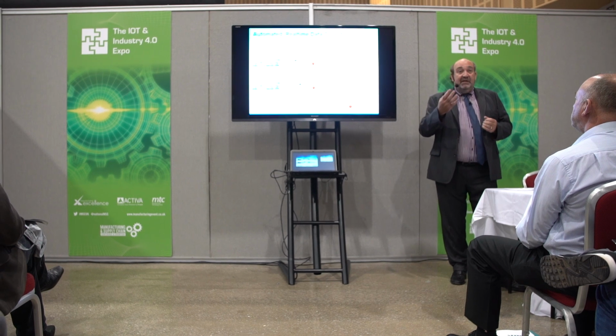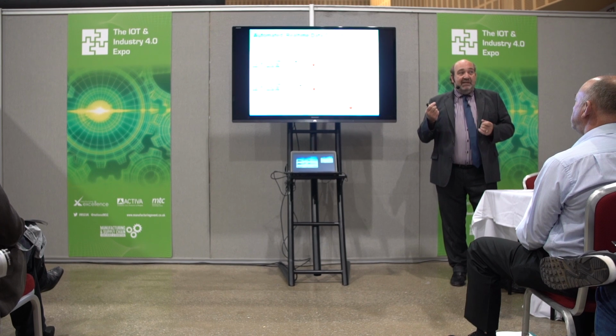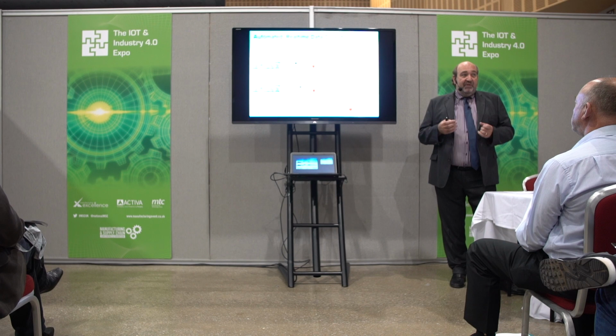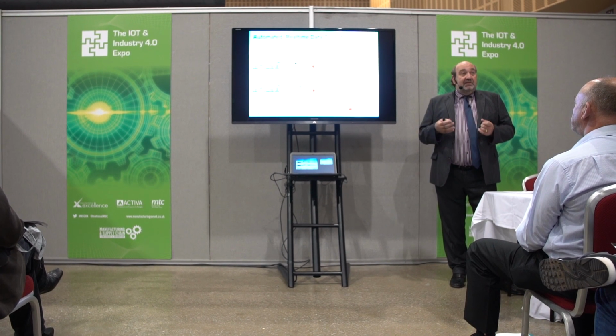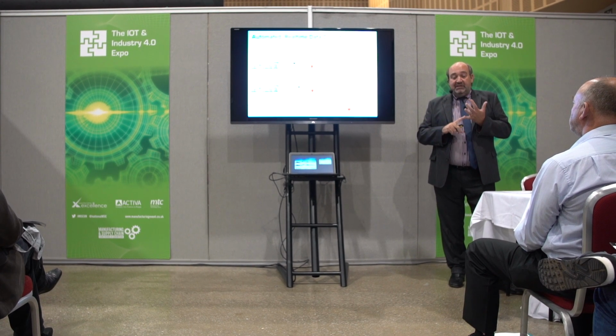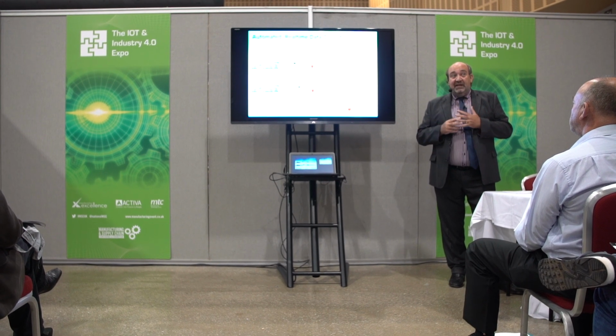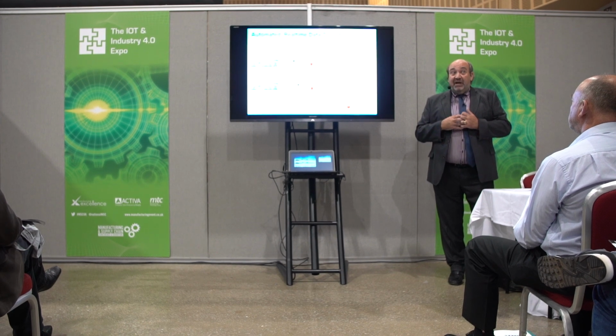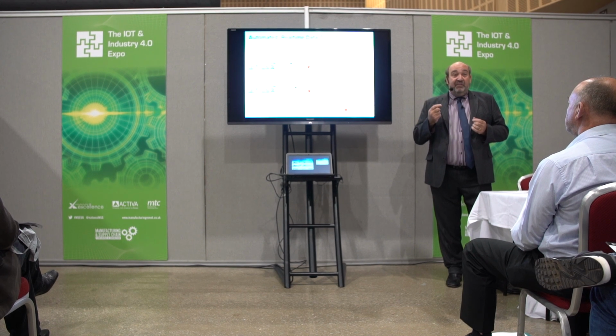A simple example is the single most essential piece of information we need to give us this kind of data, which is a count. So if we can get a count and we know that a machine is supposed to operate at 60 cycles a minute, we expect a pulse every second. So from that single piece of information, I can tell whether a machine is running. It's either generating counts or it isn't. I can tell what speed it's running at. If it's running at 60 strokes and I'm getting a pulse every second, it's at full speed. If it's running at 30, it's running at half speed. And if it's not giving me counts, if it's not giving me pulses, it's stopped. So from one simple signal, we can get some very interesting information.